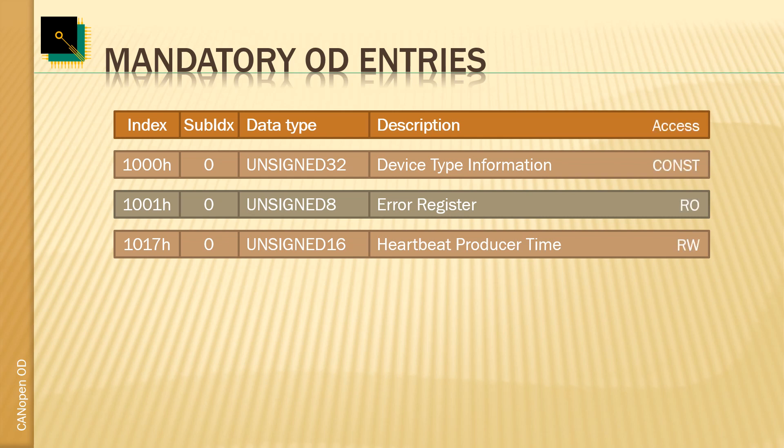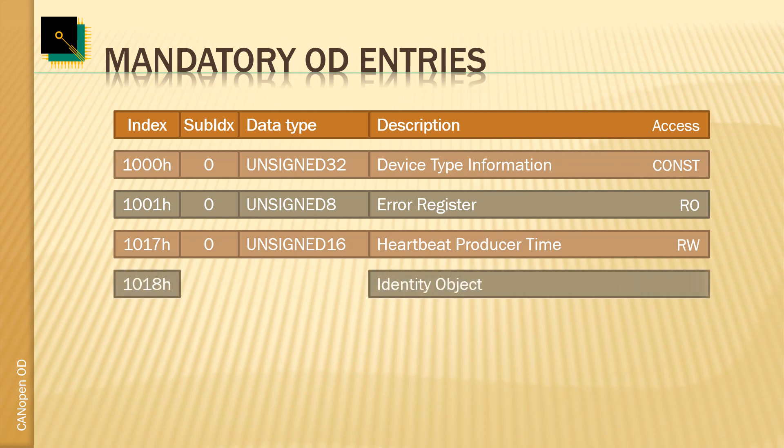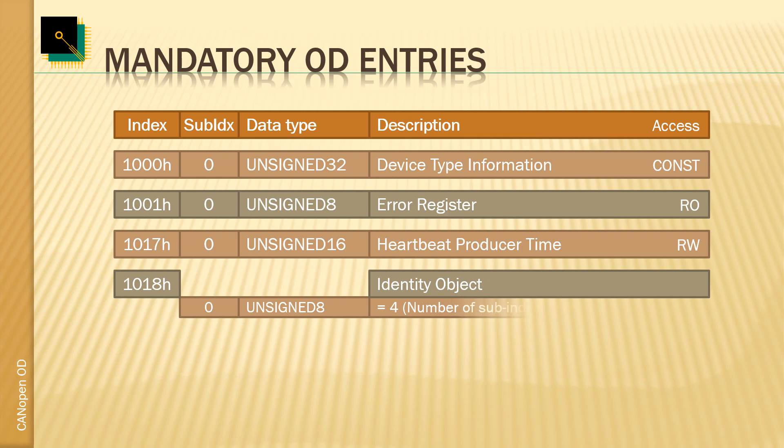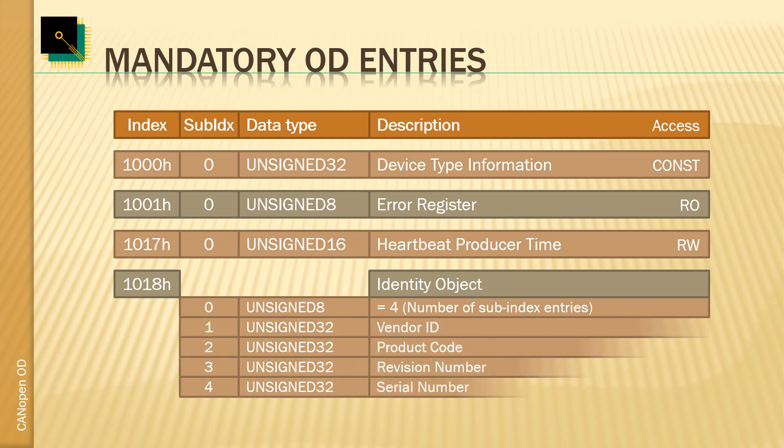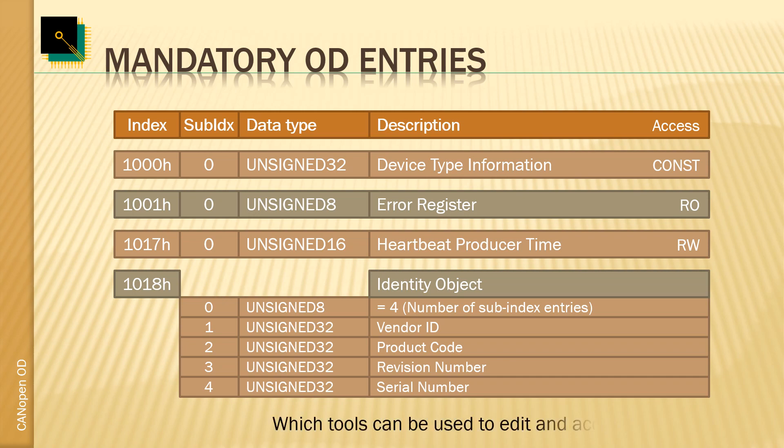The mandatory identity object at HEX 1018 is making use of the sub-index value to group multiple entries at a single index. When an entry uses multiple sub-indexes, the first entry at sub-index 0 always informs us about how many sub-indexes are available - here four. The following sub-indexes then have the grouped data elements: the parts of the identity object, the vendor ID, product code, revision number and serial number.